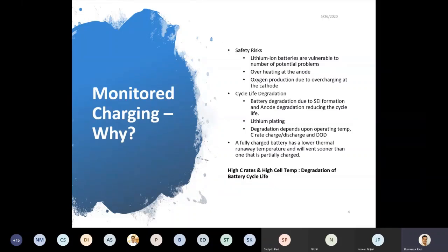Even within LFP, multiple chemistries exist. Manufacturers may add additives that change the properties of the materials and how the reactions happen, which also changes the thermal runaway temperature. But generally it is higher than 100 to 120 degrees centigrade for most cells. So once this temperature is crossed...